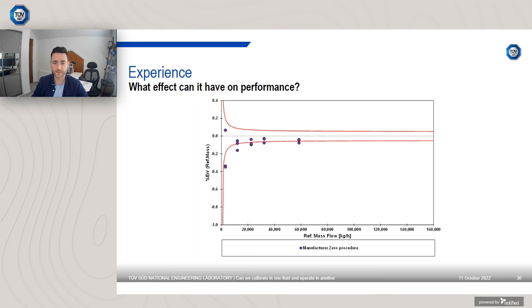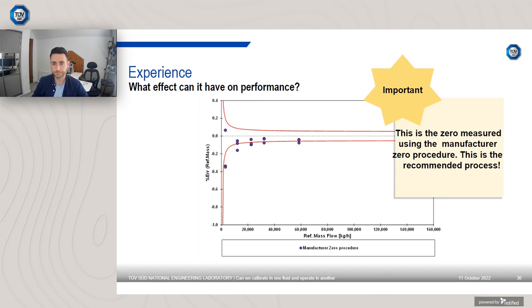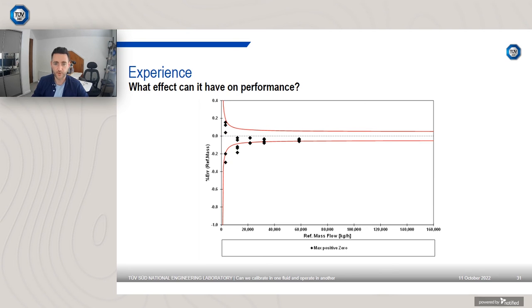Now I use the manufacturer recommended zero procedure. So we followed the procedure as detailed in the manufacturer guidelines. You can see that the results were okay, but actually had a bit of a spread, not too repeatable. I think this calibration maybe wasn't a perfect calibration. I think there was potentially secondary effects going on with this one. This is actually the recommended process, but it just so happened it wasn't a perfect calibration that was performed.